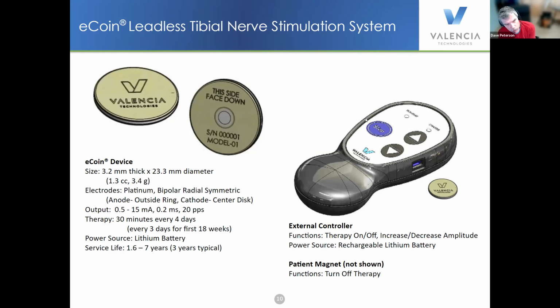The electrodes in this system are platinum, and the cathode is that center disc. I don't know if you can see my cursor here, if that helps, but this is where the cathode is. And then the anode is a ring that goes around the outside edge of the coin. And a couple of neat things about that. One, we only need one feed through in this system. This is actually an active CAN device where the CAN itself is the cathode, and then we isolate the current through this platinum disc by insulating the rest of the housing with silicone rubber.